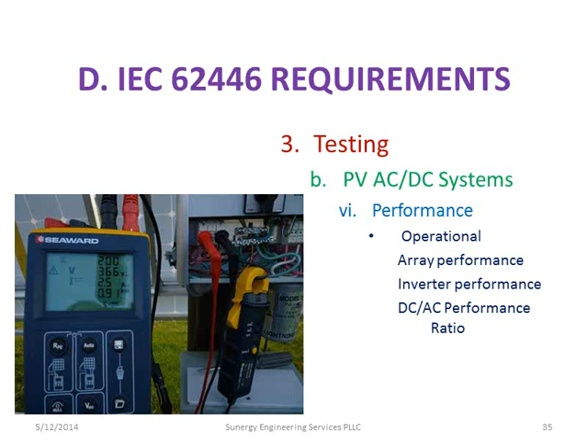I don't know anyone who's done a performance validation by having 3 meters and 2 clamp-ons and trying to record everything instantaneously. It's not as accurate, for sure, especially when you're commissioning. It's never a nice, perfectly clear day. Sun's just where it needs to be. There's no clouds. There's no wind. So conditions can change pretty dramatically, especially in these larger megawatt systems where they're having to test lots and lots and lots of these.